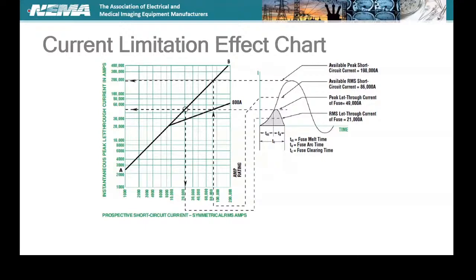So we're all familiar with that. Well, we may or may not be, the up over down method, right? What you have across the bottom is your RMS symmetrical short circuit current. If you go all the way up to the B line and over, that tells you the peak of the asymmetrical current. So for 86,000 amps of RMS short circuit current, the peak is 198,000 amps. And if you have a current limiting 800 amp fuse in that picture, you reduce the peak from 198,000 amps all the way down to 49,000 amps. So that's a significant reduction in the peak. And then from an RMS perspective, you've reduced that down to 21,000 amps RMS, which is root mean square.